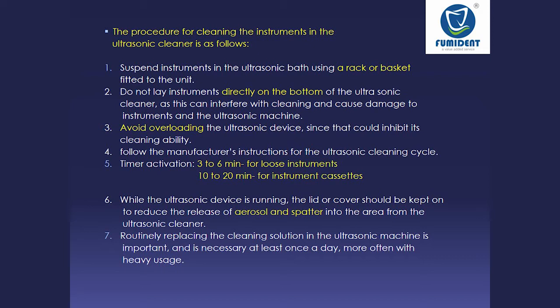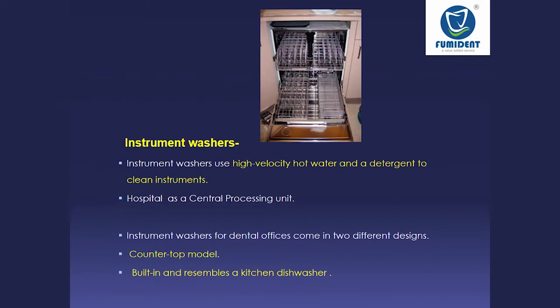Then the next machine which you can use is the instrument washer. The instrument washer uses high velocity hot water and detergent to clean your instruments. So most hospitals use this in the central processing unit. For dental offices also there are two machines available. The one is a countertop model and another is built in and resembles a kitchen dishwasher. So generally this much heavy machine is not required for a dental clinic.